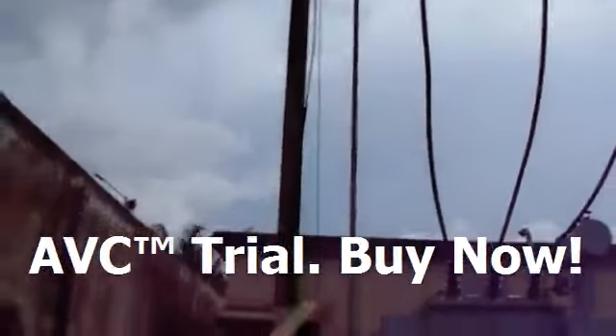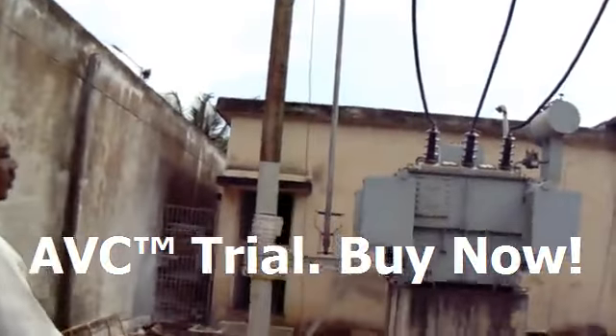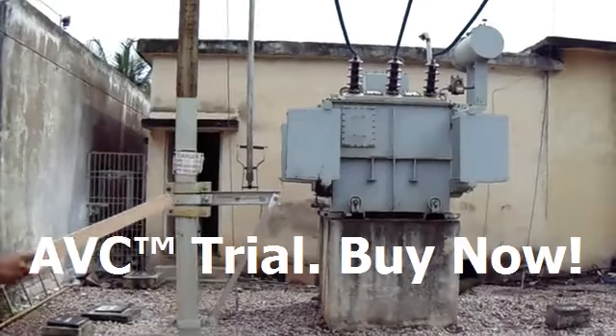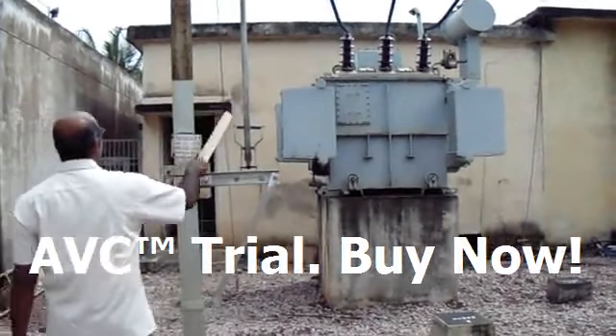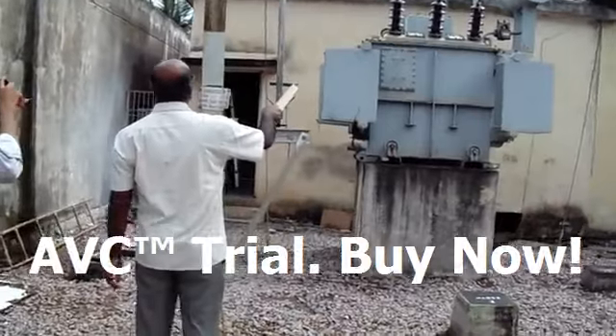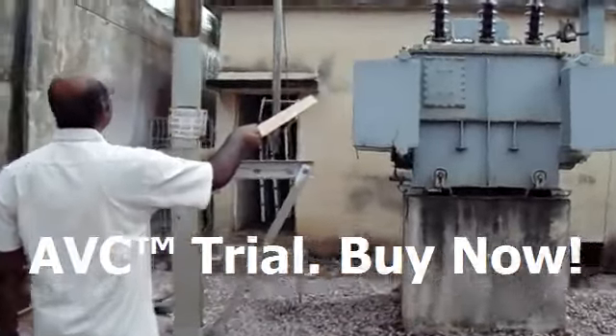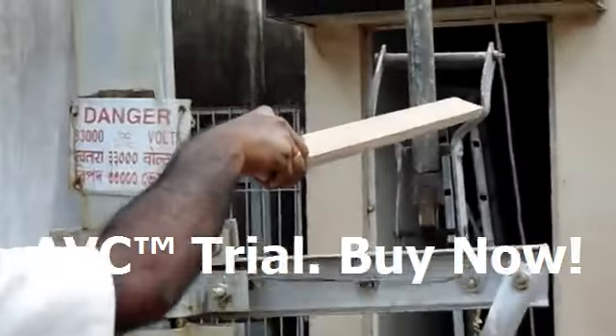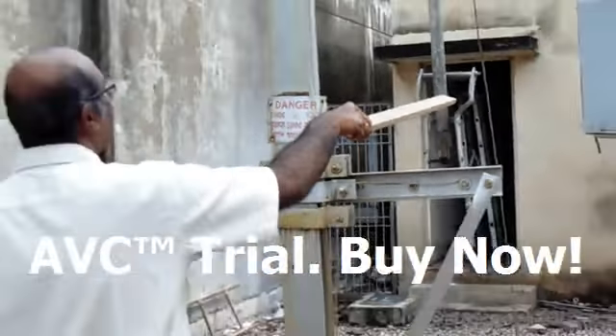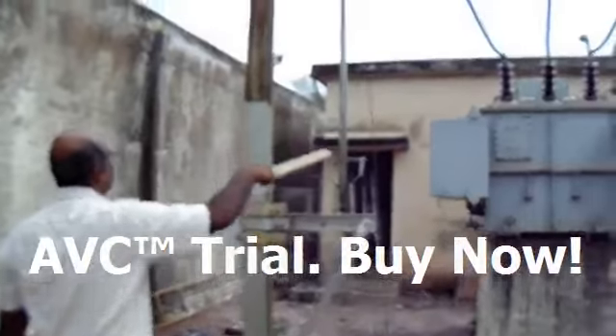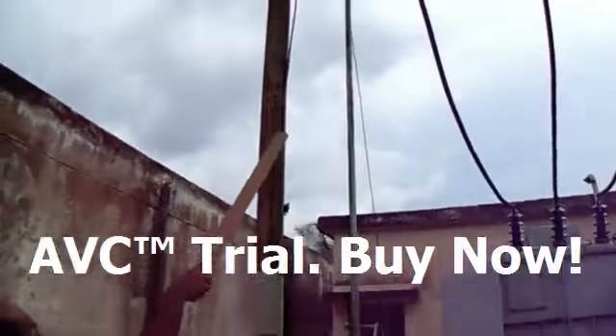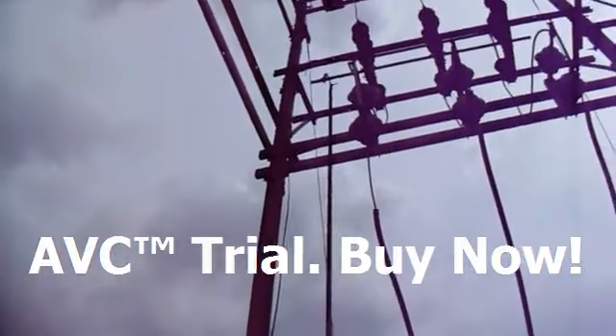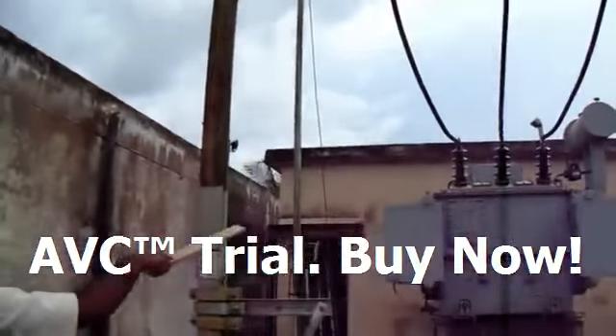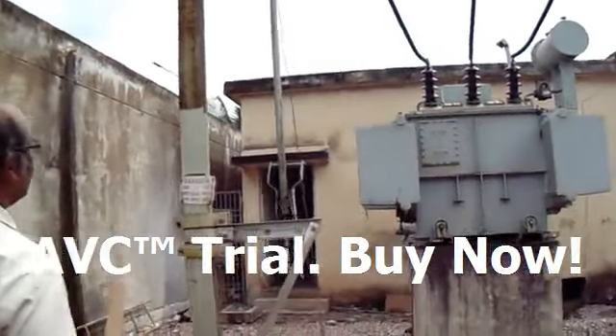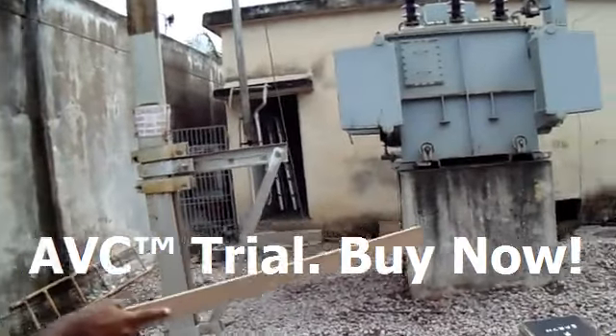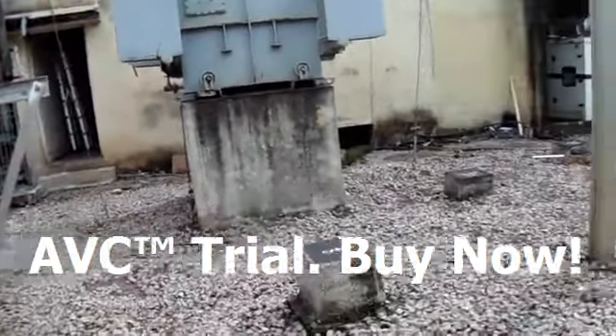We have earthing for the substation structures, and then you have earthing for the EB switch. This is again an off-load disconnector. So whenever you want to take your transformer into maintenance, you have to open this air break switch. This is not an on-load disconnector. This is an off-load disconnector. That means first you have to switch off the load, then you open this air break switch. So there will be 4 to 5 earthings in a typical substation.